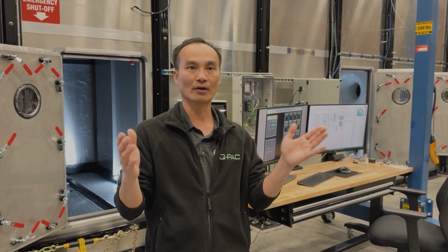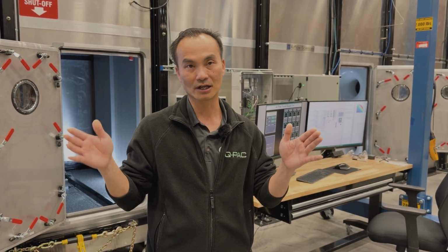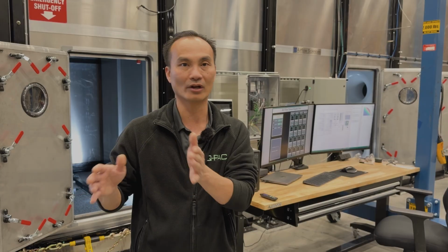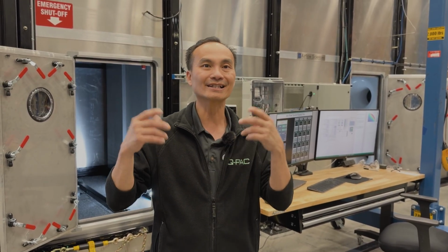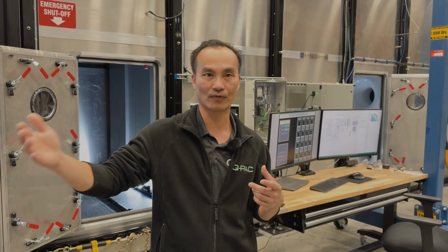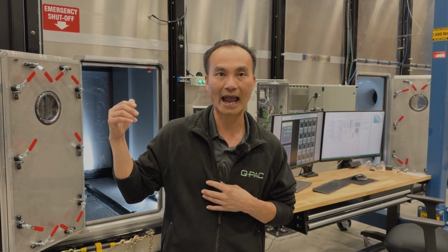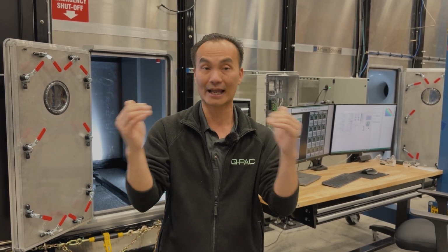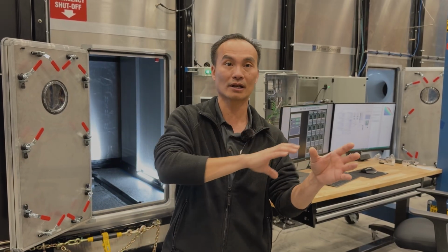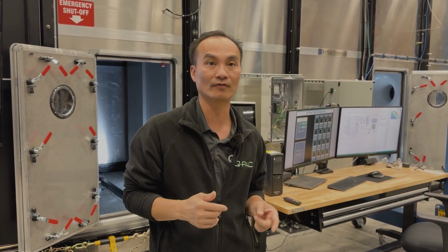The sweet spot is where it's the most energy efficient. For example, sometimes you have an air handling unit or fan system designed at 70,000 CFM. But at certain times in the day, the fan system doesn't work at 70,000 CFM. It only works at halfway or even less than that. What is the best way to run this fan system, deviating from the original design? The seasons change, the airflow through the building changes, and this and that, right? Today we lock in the way all the fans have to operate at the same setting. But in the future, you don't have to. Certain fans can be run idle or at a lower operating point to save energy and extend their lifetime, while the other fans can switch their spot to use the least amount of energy and run the fan system most efficiently, according to the environment it's provided.